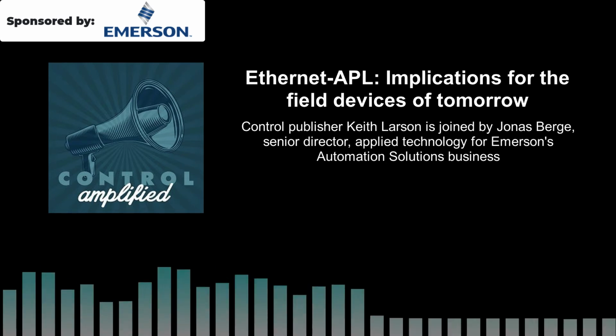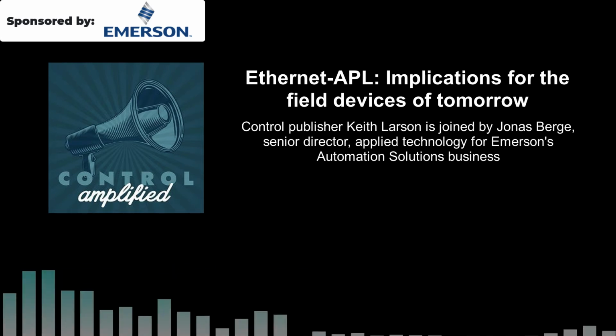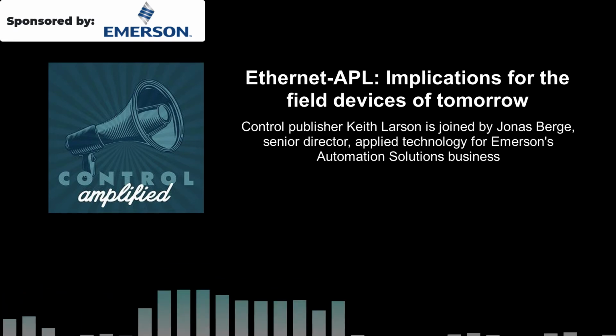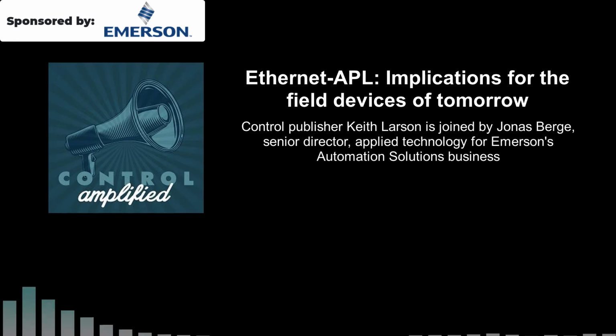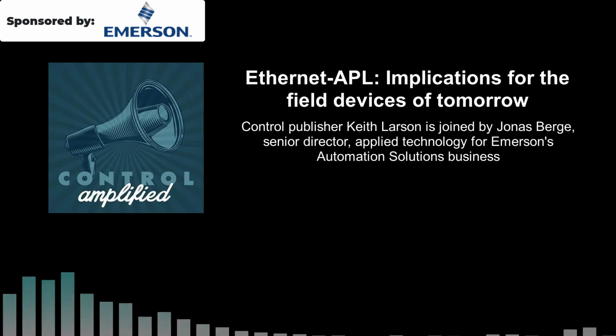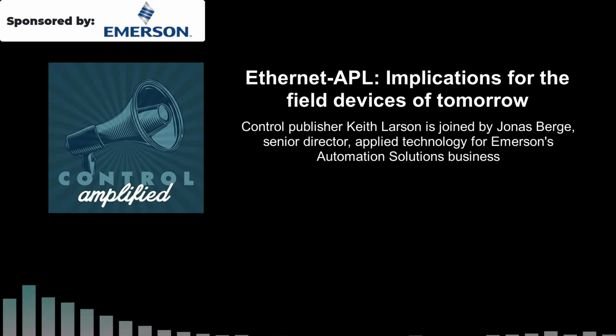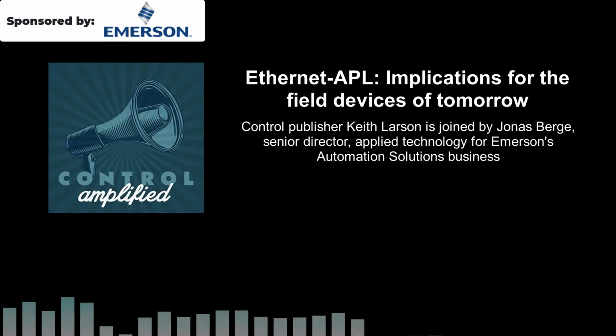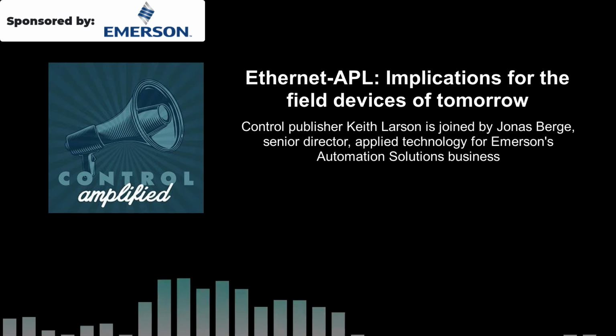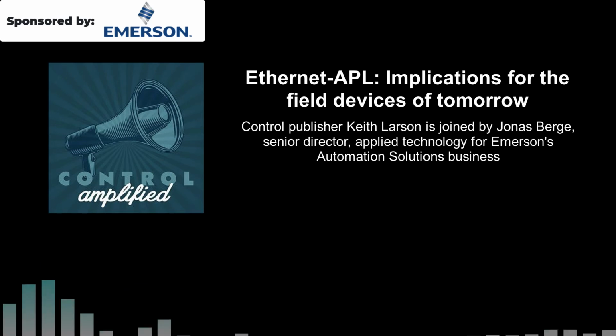And maybe also, for the type of instrumentation such as transmitters and valve positioners we are familiar with, the greater bandwidth that you also get with APL means a higher speed. So you can put more devices on a network than with traditional fieldbus and still get faster response time. So yeah, you don't need as many networks as you did with fieldbus.